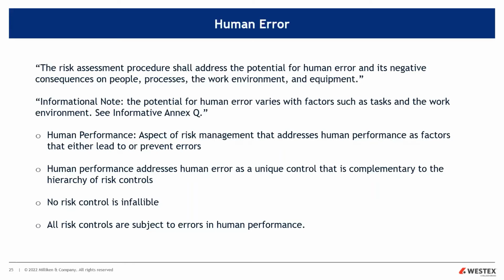Complacency, procrastination, lack of knowledge, lack of experience, all human error precursors that can impact the risk assessment procedure and when to reassess the hazard. So, have the changes or additions impacted the electrical equipment's available fault current and clearing times? Can the PPE category method still be used? If it can't be used, then we need to do the incident energy analysis or the arc flash study. That needs to happen. Certainly, human performance impacts the risk assessment procedure. So make sure qualified safety personnel and qualified electrical engineers that are called on to perform the arc flash hazard assessment are cognizant of these error precursors and free from these error precursors to better perform the risk assessment or the updated reassessment with the latest tools, such as IEEE 1584, the 2018 version. So they can do that at the appropriate called for intervals.